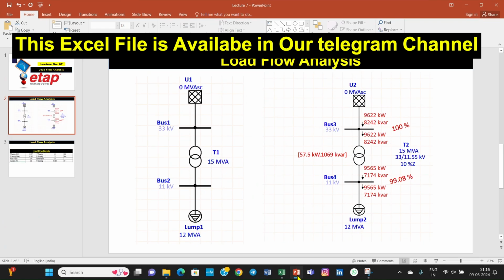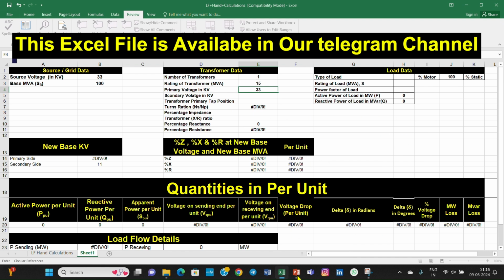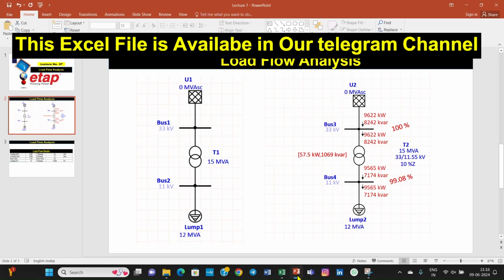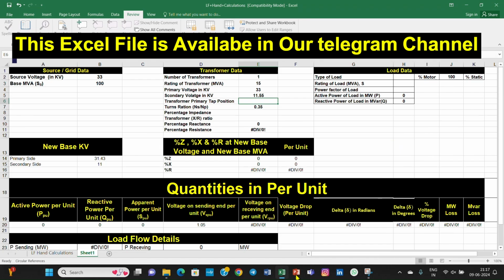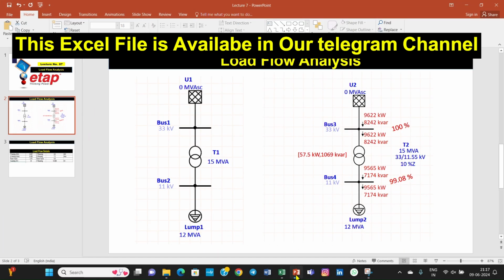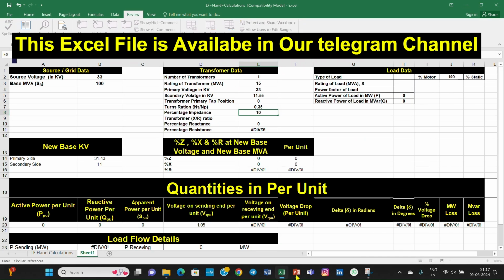Primary voltage is 33 kilovolt, and secondary is 11.55. You can see here 11.55. Tap changing is 0. This is the turns ratio. It is calculated by the Excel sheet by itself using a formula that I have incorporated. Percentage impedance here is 10%, so I can write 10.